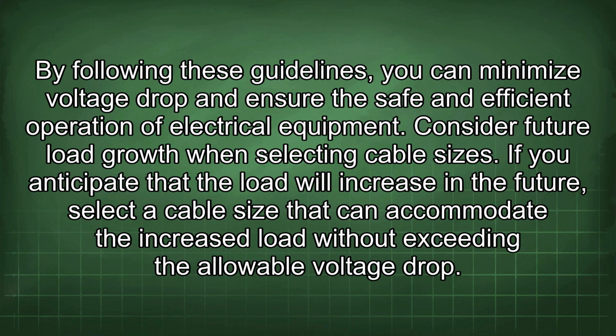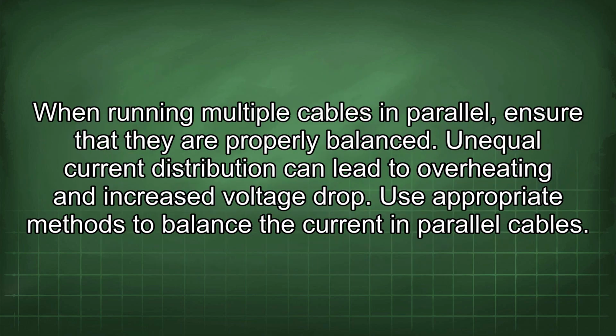Consider future load growth when selecting cable sizes. If you anticipate that the load will increase in the future, select a cable size that can accommodate the increased load without exceeding the allowable voltage drop. When running multiple cables in parallel, ensure that they are properly balanced. Unequal current distribution can lead to overheating and increased voltage drop. Use appropriate methods to balance the current in parallel cables.